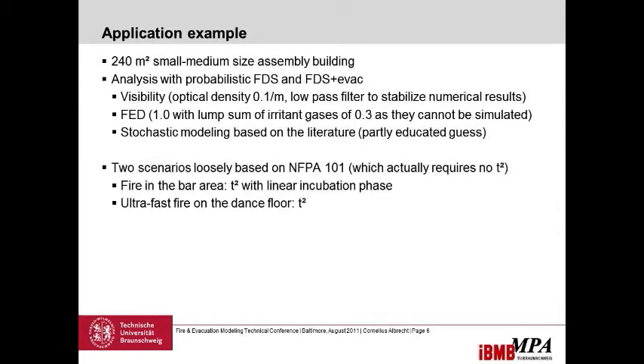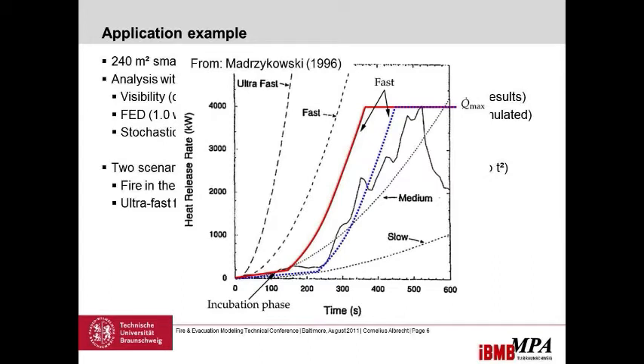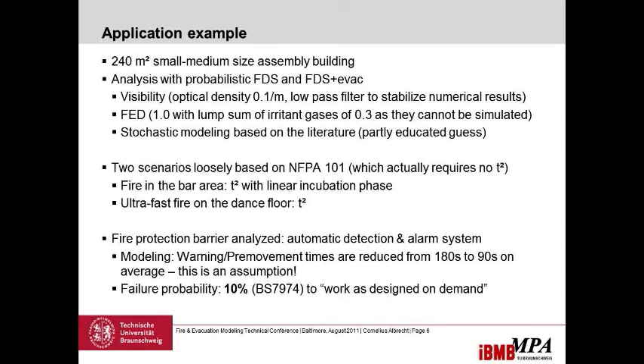Two scenarios were considered loosely based on NFPA 101: one is a fire in the bar area using a T-square fire with a linear incubation phase, and the other is an ultra-fast T-square fire. Fire experiments show there's always a little incubation phase, so I included that because using a pure T-square scenario for life safety is very conservative. The fire protection barrier analyzed was an automatic detection and alarm system, modeled by reducing the warning and pre-movement time from 180 seconds to 90 seconds.